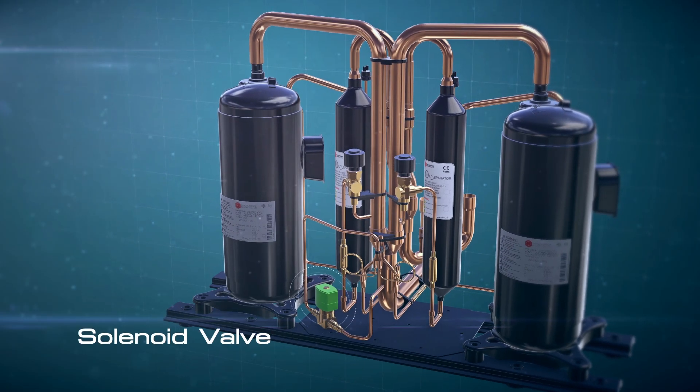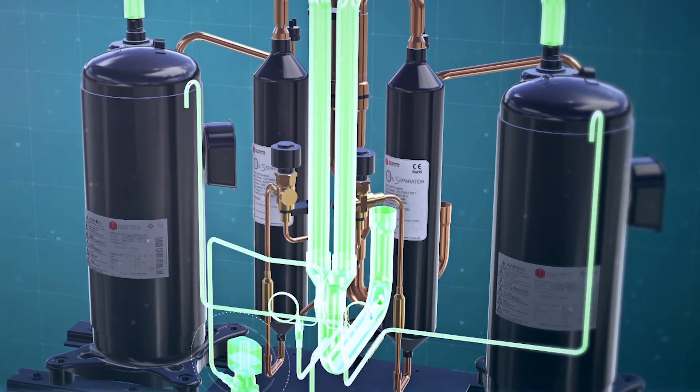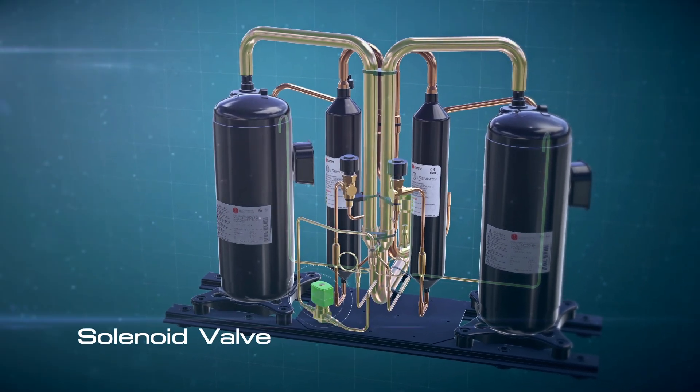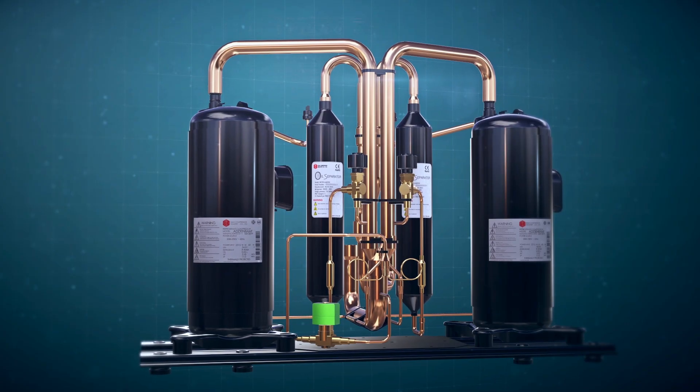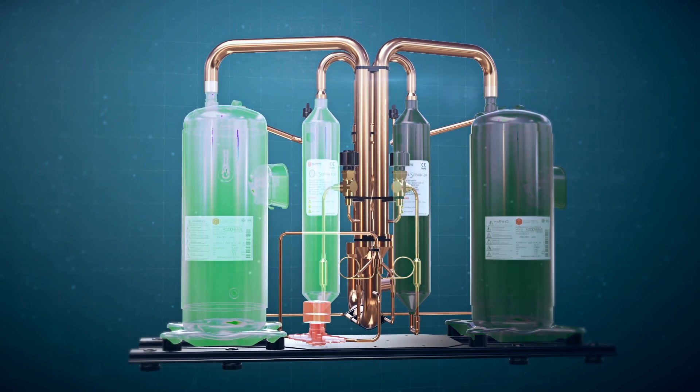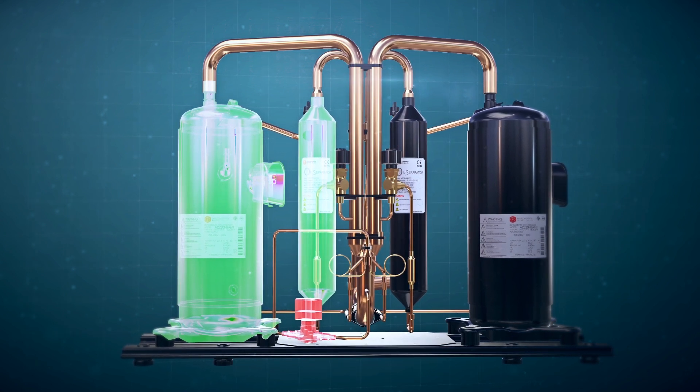Moreover, a solenoid valve is needed per one plural compressor set by connecting the manifold oil balance pipe to the solenoid valve, then to the manifold suction pipe. The solenoid valve will open when more than one compressor is working at the same time and will close when only one compressor is working.